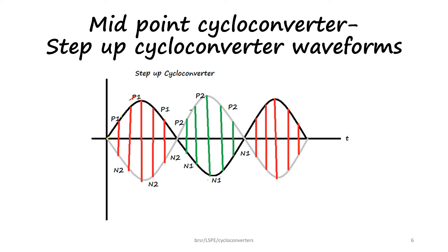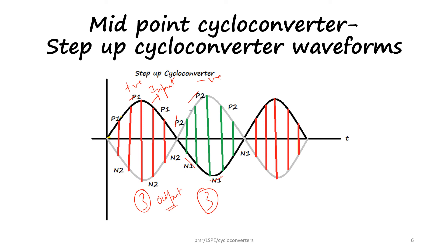In the negative half cycle, P2 and N1 are switched alternatively, just as P1 and N2 were switched in the positive half cycle. In the positive half cycle P1, N2 is turned on three times, and similarly in the negative half cycle P2, N1 is turned on three times. So in one complete cycle of the input voltage we have three output cycles in the positive half and three in the negative half, giving 6 output cycles total. By switching at a different rate, the required output frequency can be obtained.